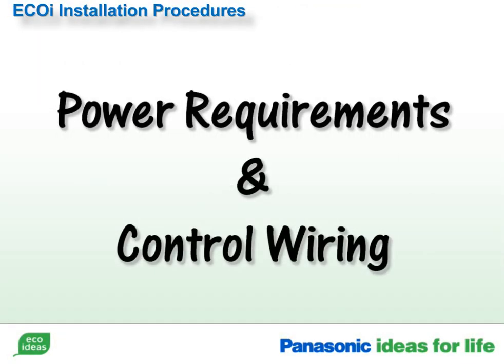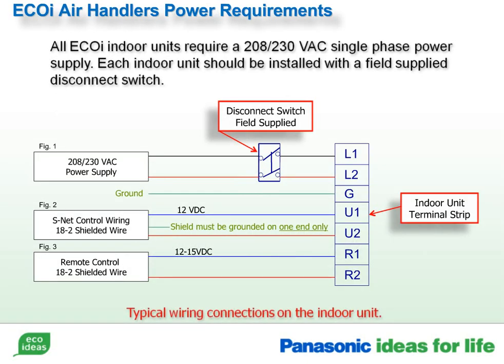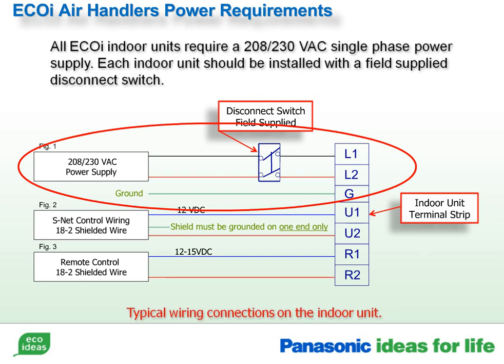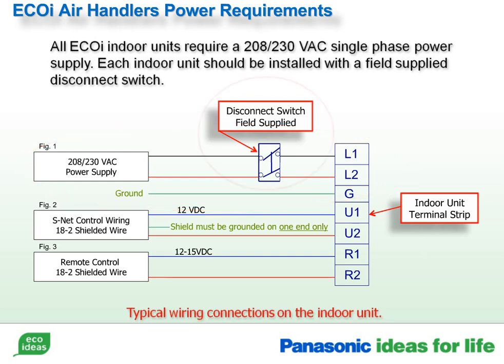Power requirements and control wiring. This is an example of the wiring typically found on the indoor unit. All indoor units require a 208, 230-volt power supply, and it is not uncommon to connect as many as 5 indoor units on one power supply circuit, if permitted by your local codes.